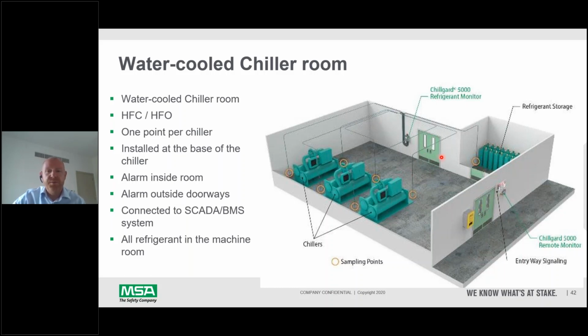It's important also to put a detector in the refrigerant storage area in case there's a leak there. The system should also be connected to the local SCADA or BMS system to alert the user remotely that there is a leak. If we can detect at very low levels, which we do with the ChillGuard at 1 ppm, you can prevent a small leak from becoming a much larger leak for the operator.